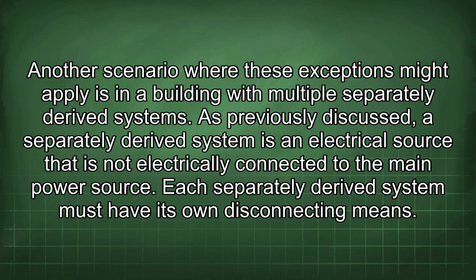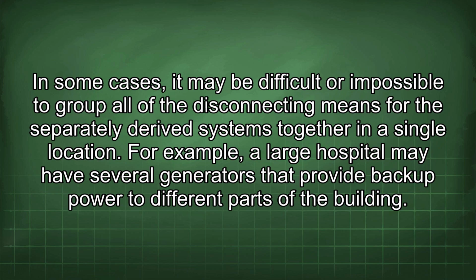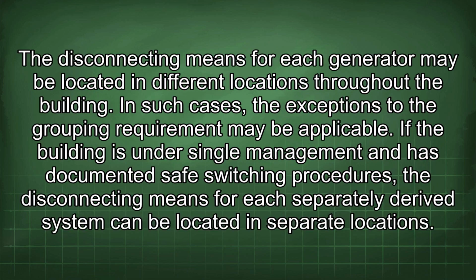Another scenario where these exceptions might apply is in a building with multiple separately derived systems. As previously discussed, a separately derived system is an electrical source that is not electrically connected to the main power source. Each separately derived system must have its own disconnecting means. In some cases, it may be difficult or impossible to group all of the disconnecting means for the separately derived systems together in a single location. For example, a large hospital may have several generators that provide backup power to different parts of the building. The disconnecting means for each generator may be located in different locations throughout the building. In such cases, the exceptions to the grouping requirement may be applicable.